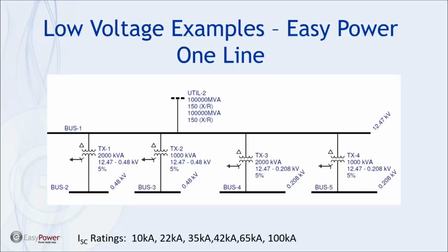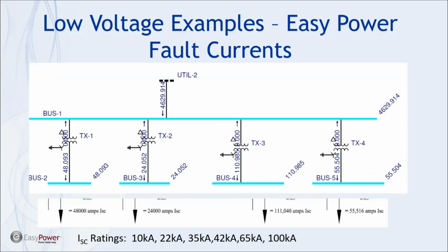So now going to EasyPower. Here's the one-line diagram in EasyPower for those 4 transformers. And to me, when we look at utility 2 here, this is EasyPower's default representation for what I would call an infinite bus. And so that's the one-line diagram. And then here are the fault currents that are generated with those transformers, with those ratings and impedances.